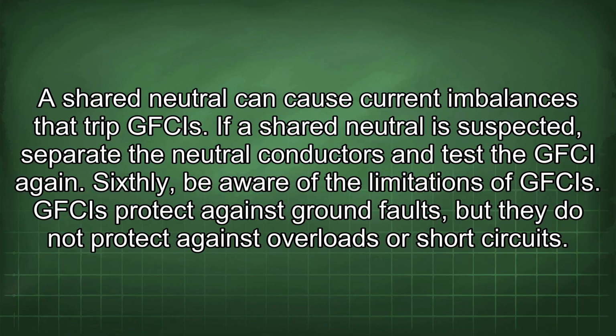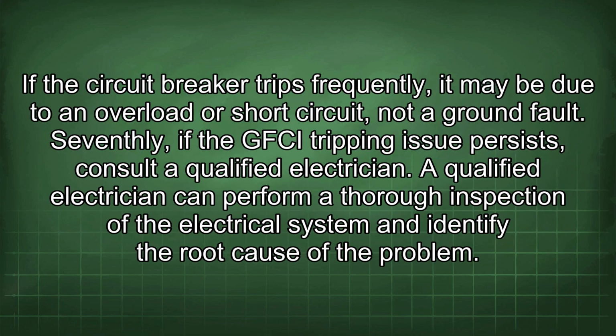Sixthly, be aware of the limitations of GFCIs. GFCIs protect against ground faults, but they do not protect against overloads or short circuits. If the circuit breaker trips frequently, it may be due to an overload or short circuit, not a ground fault.